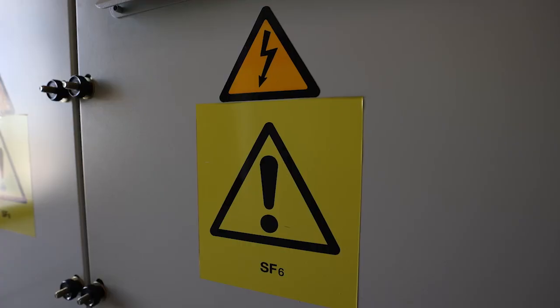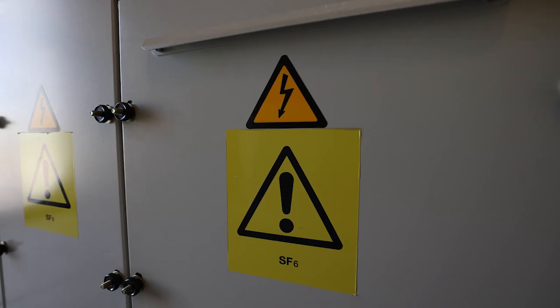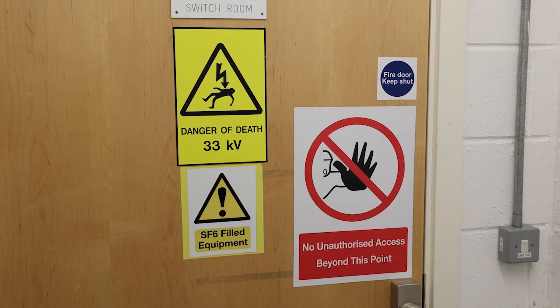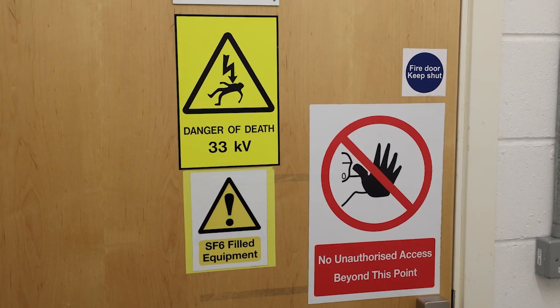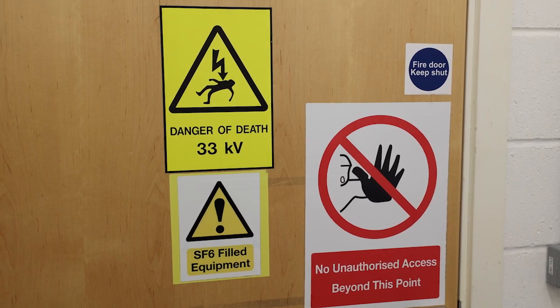Also, smells like burnt plastic can indicate an electrical fire, and the smell of rotten eggs could indicate the presence of decomposed SF6 gas. SF what? SF6 gas. It's used in some switchgear to reduce arc flash. It's inert and has no smell, but if it's been exposed to an electrical arc, then it will smell of rotten eggs. So if you smell it, you shouldn't enter the space as the risk of electrical arc will be high.